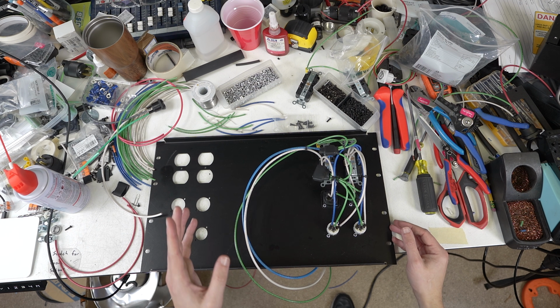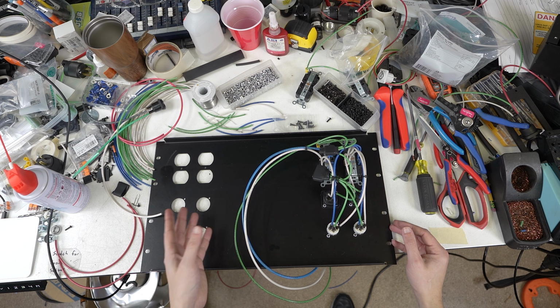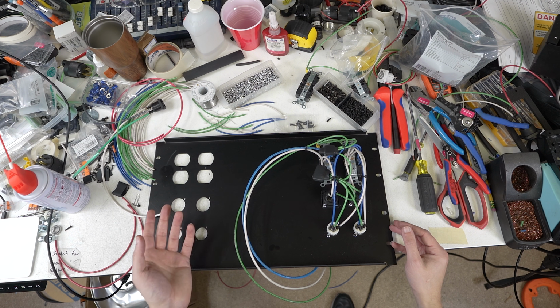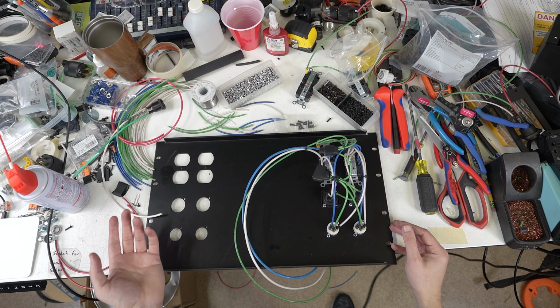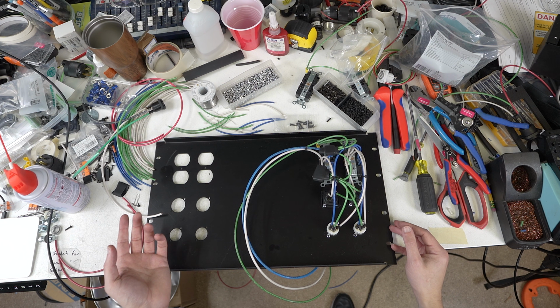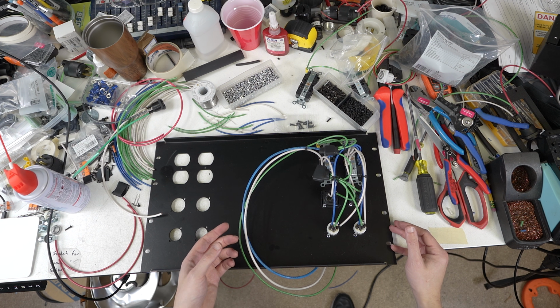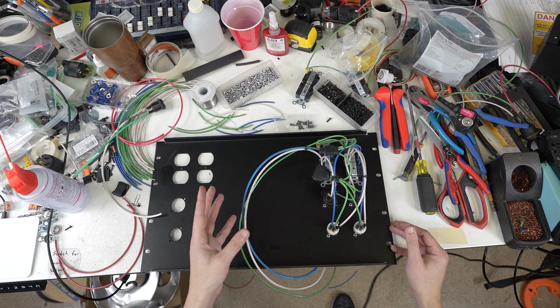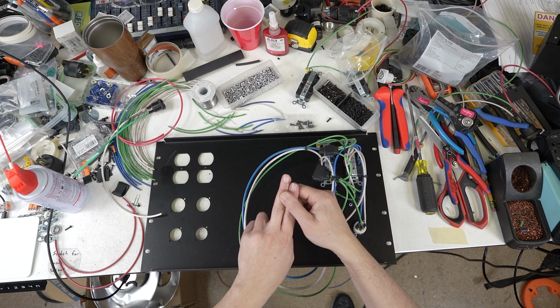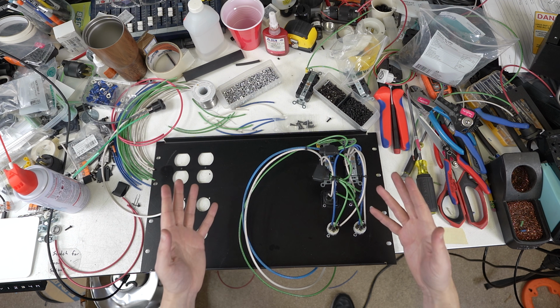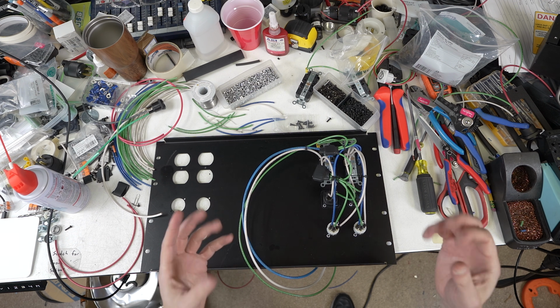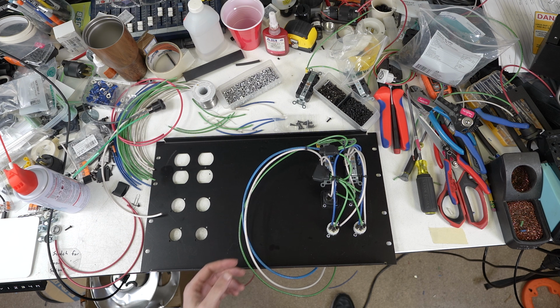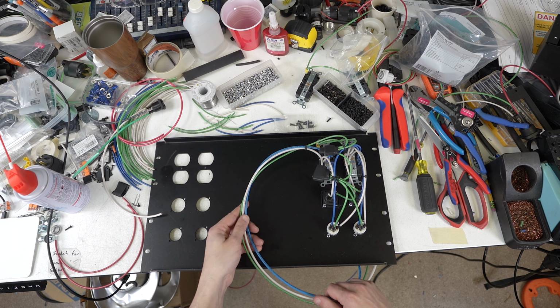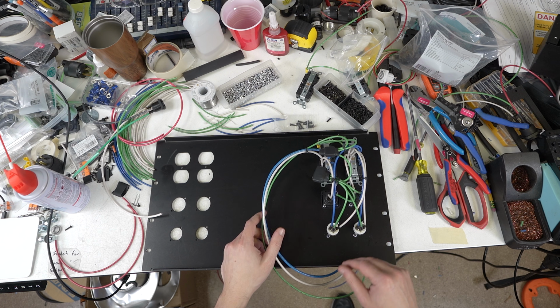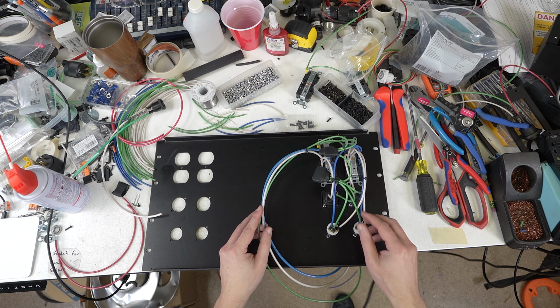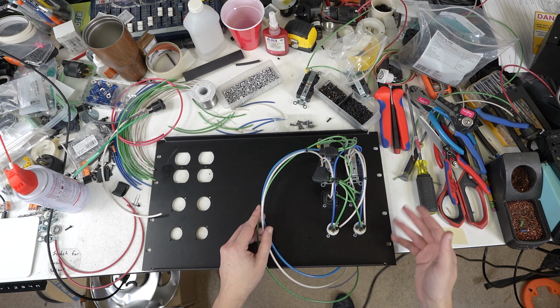As a matter of fact, we had an electrical short here earlier in the week which took one of our CNC pumps down all day. Those run at 480 — they're 480 Delta motors with 60 amps a leg, and when it came from the factory, there were two connections in a wire nut that were arcing. Over time it heated up too much, melted the wire nut, and went into a big arc flash of 480. I had to rewire that thing earlier in the week, which further cements my hatred of wire nuts — and that's in a static application just here in our shop.